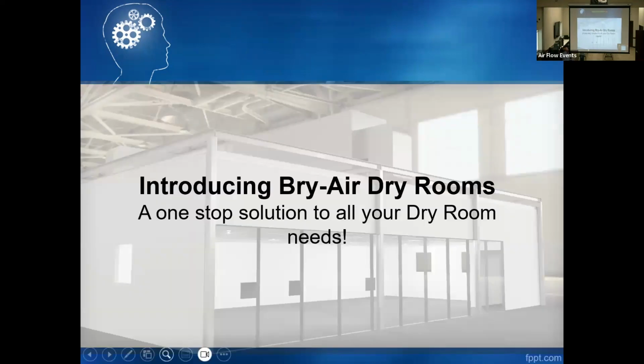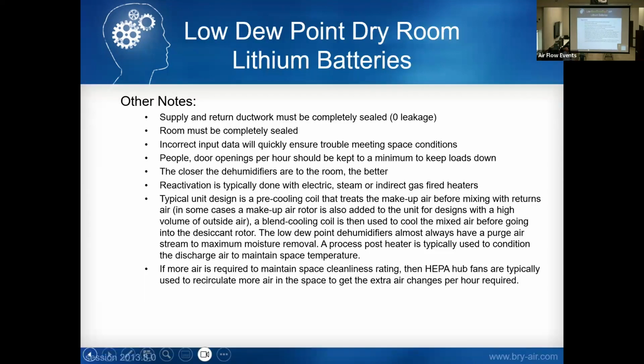Oh, one other thing here. One of the things we do in these, and Tom, we could talk about other applications, is that these types of rooms typically require a lot more sensible cooling or air changes per hour. You need cleanliness ratings, ISO cleanliness 10,000, those types of ratings. So we're talking 60 air changes an hour. In a lot of cases, you don't need that much dehumidification. So one of the things we do in these markets is use HEPA hub fans in the room, in the plenum, to circulate the air changes per hour as required and to do additional cooling. We'll incorporate sensible cooling on those HEPA hubs to handle that additional cooling, just to cut down on the dehumidification. Right. Size and cost.